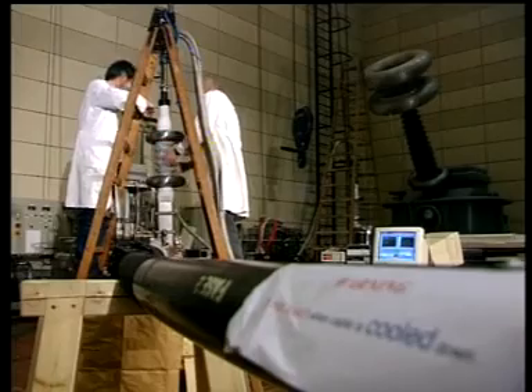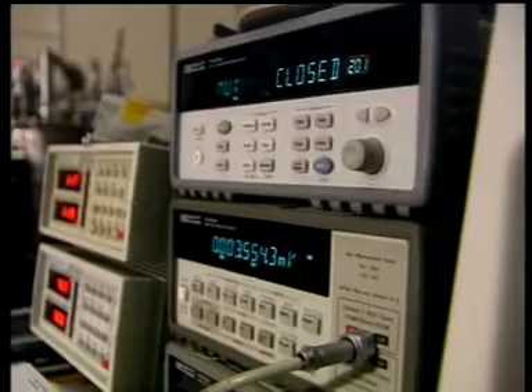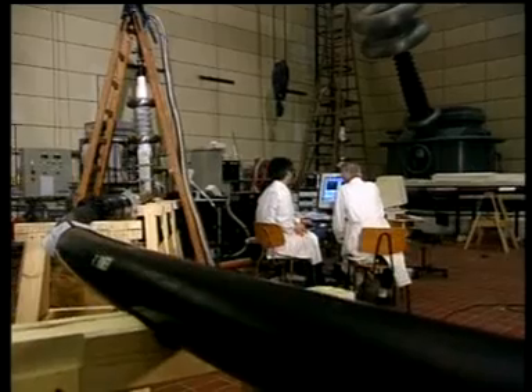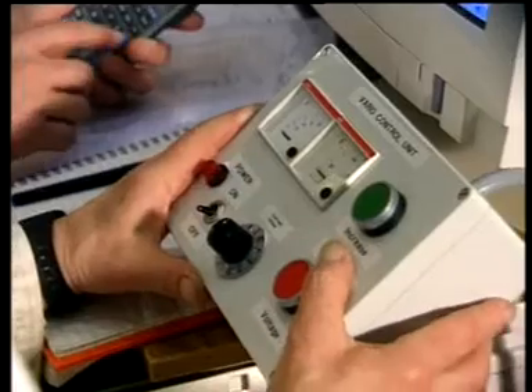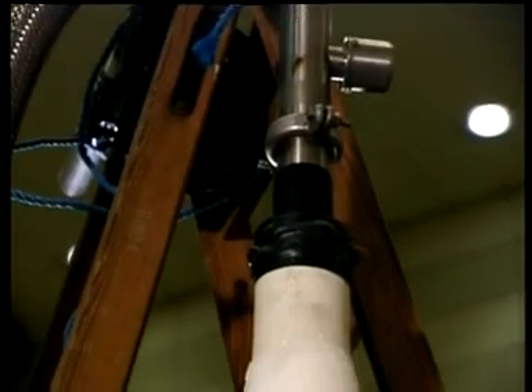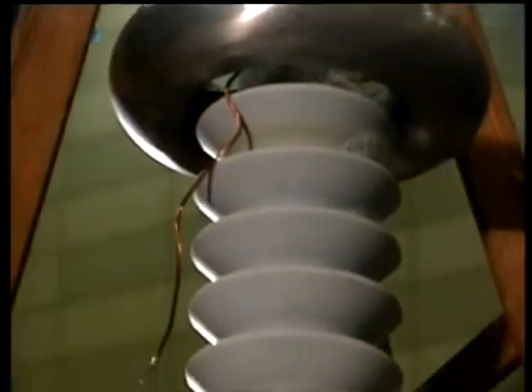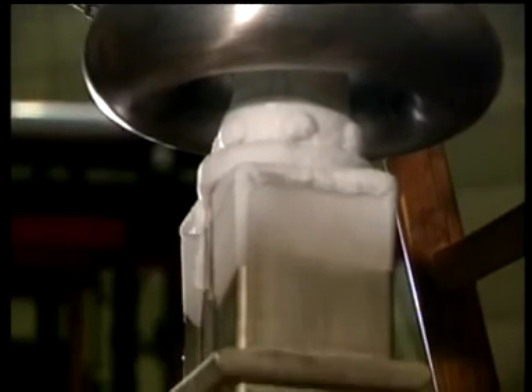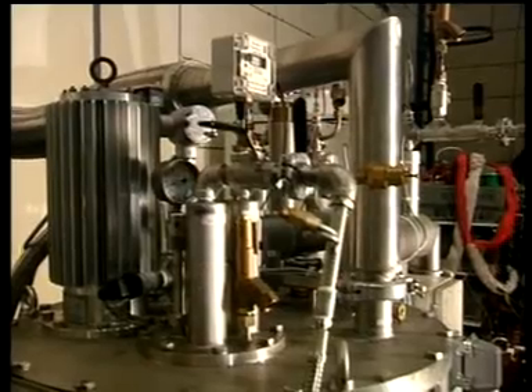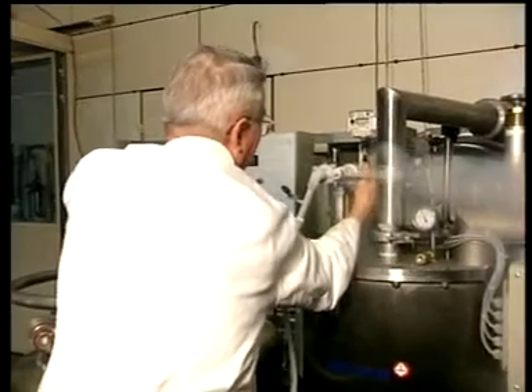And then there are the technology and physics behind the superconducting cable, which is much more advanced than in a conventional cable. You have to work with vacuum, and you have to work with electrical insulation, you have to work with very high currents, you have to work with cold temperatures. So this has been a very big challenge and also very big satisfaction to work with, I think. A tape like this, when it's cooled down, it can take more than 50 amps. One of the greatest milestones in a project like this is the invention of how to make wires out from powder. I think this cable is really a success.